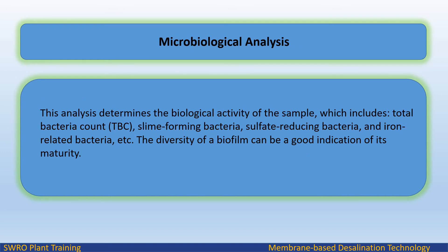Microbiological analysis: This analysis determines the biological activity of the sample, which includes total bacteria count (TBC), slime-forming bacteria, sulfate-reducing bacteria, iron-related bacteria, and others. The diversity of a biofilm can be a good indication of its maturity.